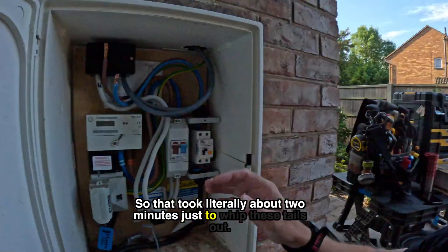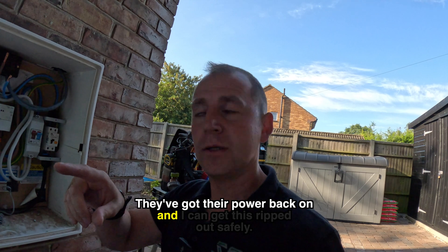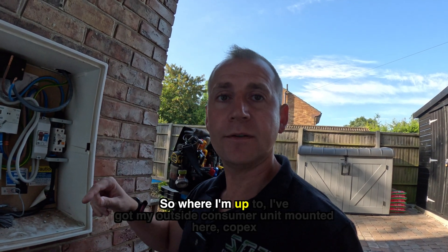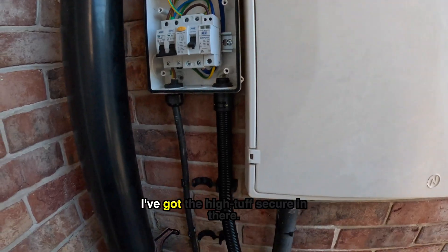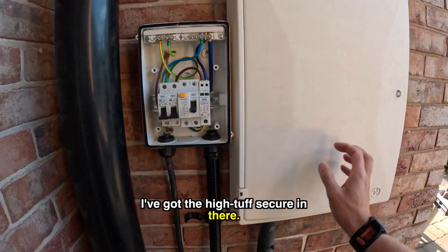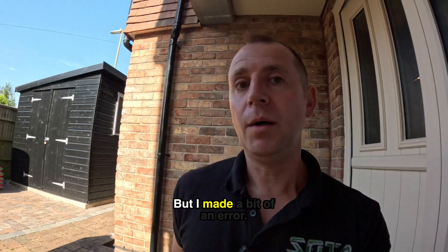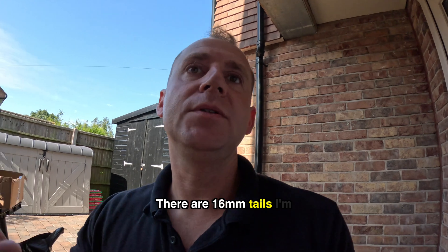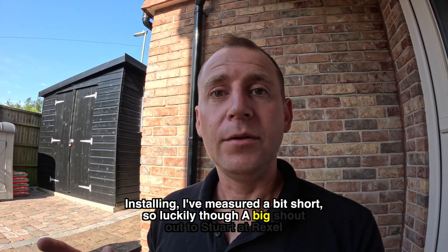That took literally about two minutes just to whip these tails out. Now this is completely isolated, they've got their power back on, and I can get this ripped out safely. I've got my outside consumer unit mounted here with copex and the Hi-Tuff secure in there. In the meter box I put a little Wiska box joining up those CT connections, but I made a bit of an error — there are 16mm tails on my install and I measured them a bit short.